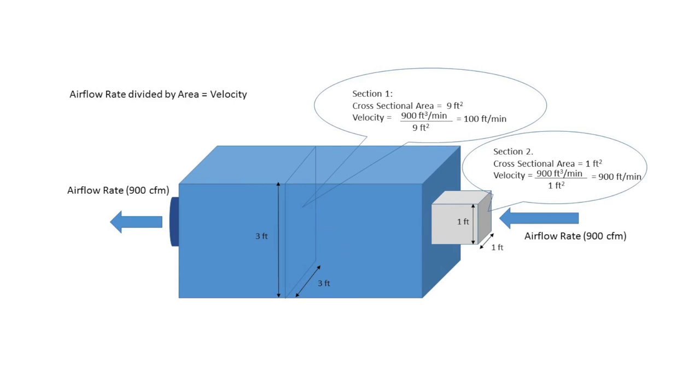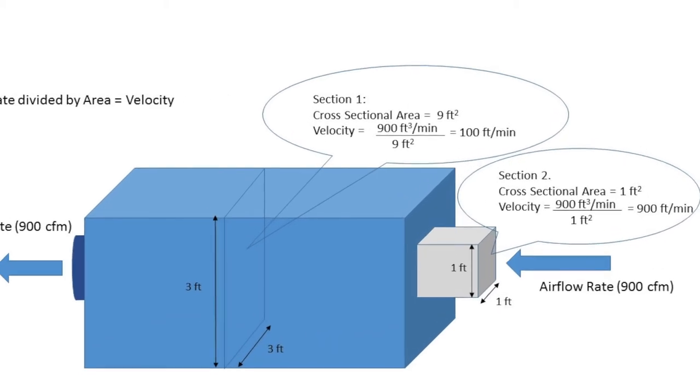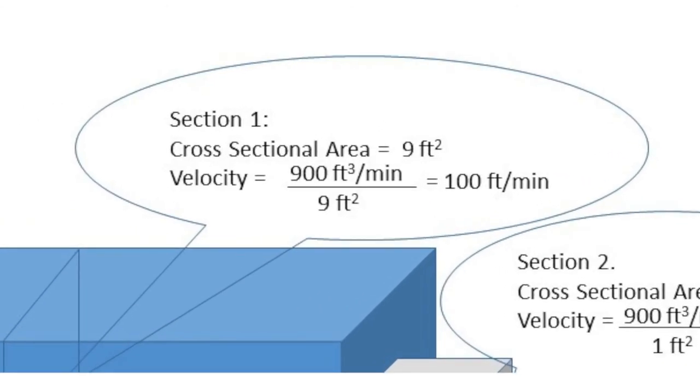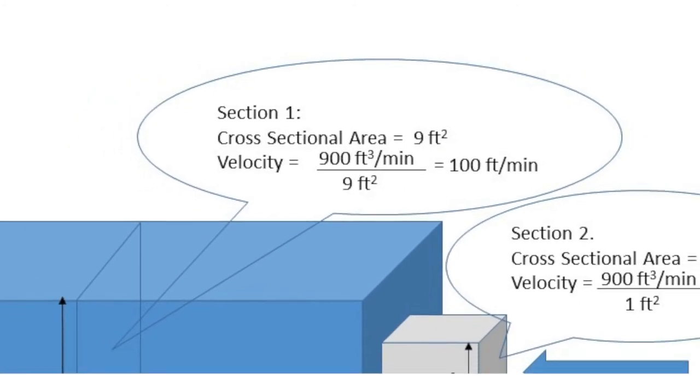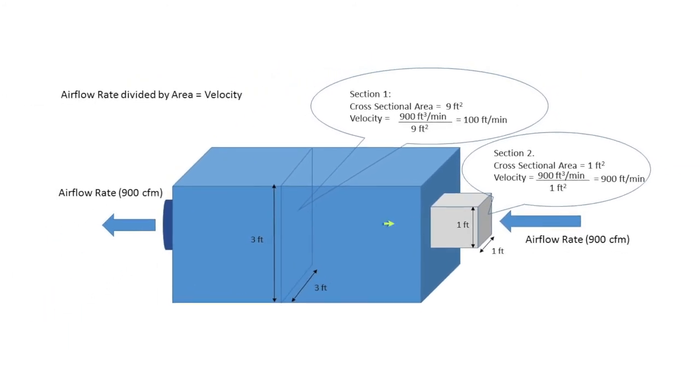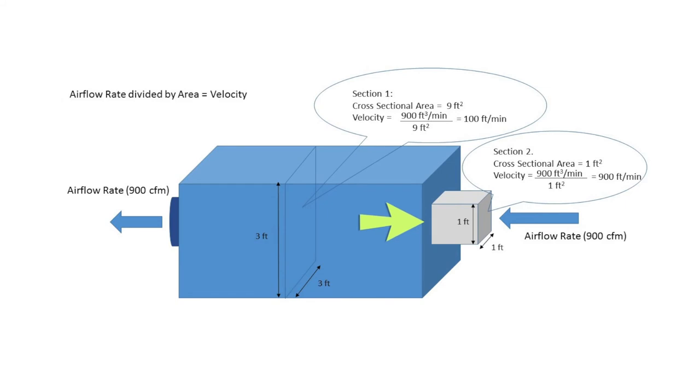Reducing this area will result in increased velocity, as shown by this diagram. In this system, the airflow rate is 900 cubic feet per minute. Looking at the larger cross-sectional area of 9 square feet, the velocity is calculated by dividing 900 cubic feet per minute by 9 square feet, resulting in a velocity of 100 feet per minute. Now see what happens when the area is reduced to 1 square foot. The velocity increases to 900 feet per minute.